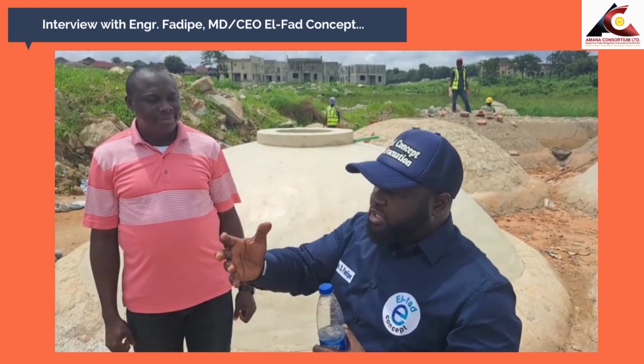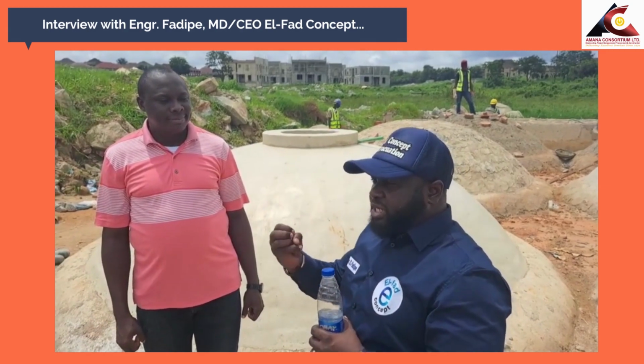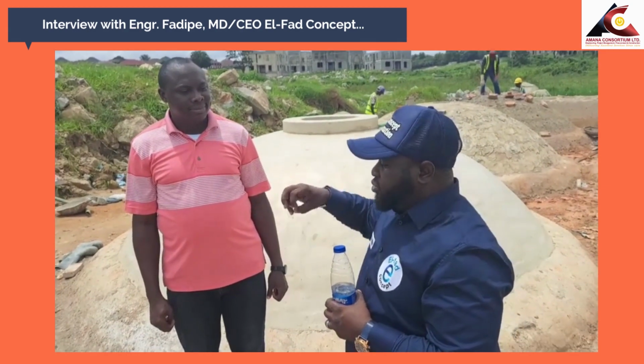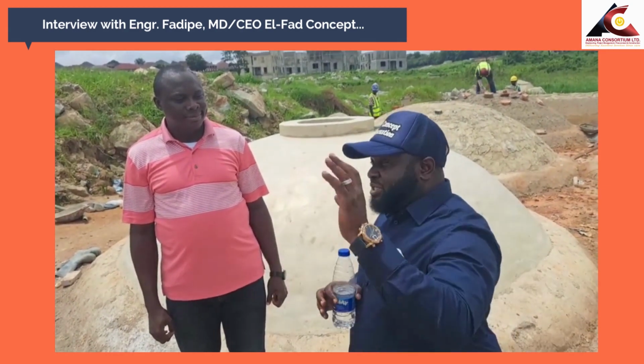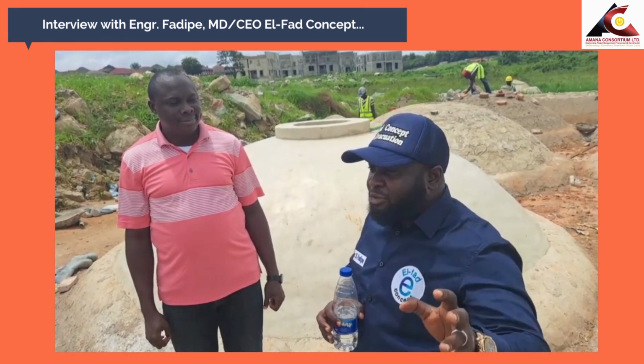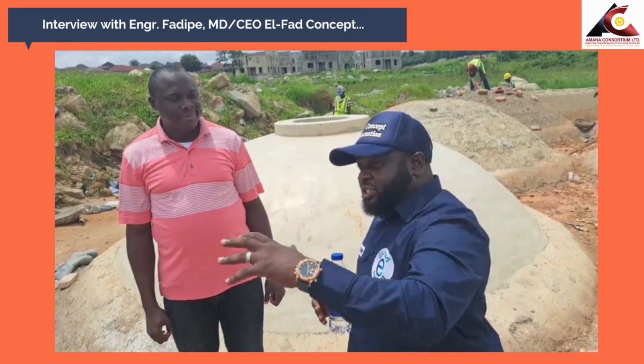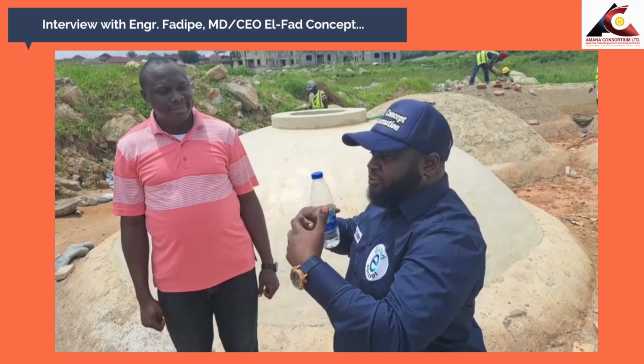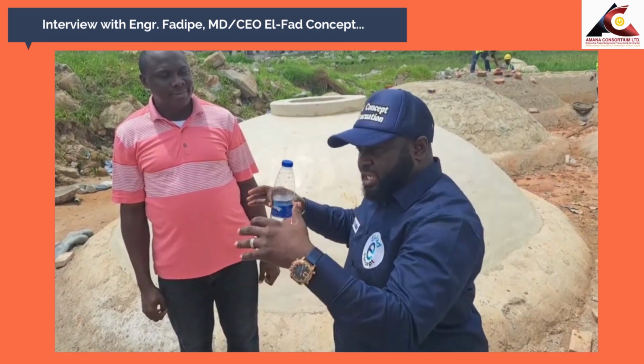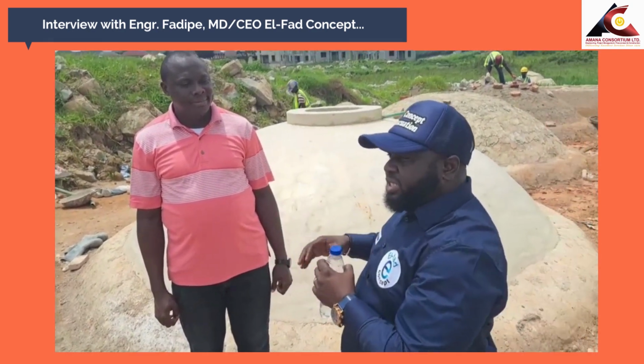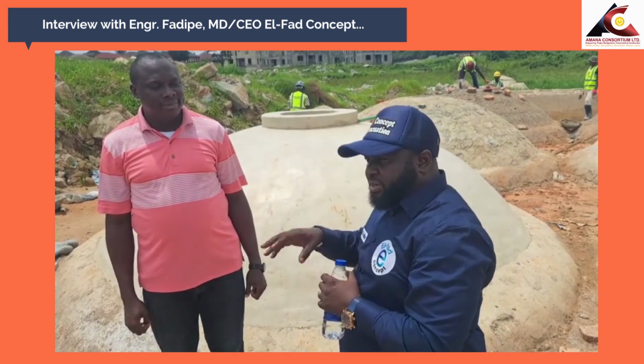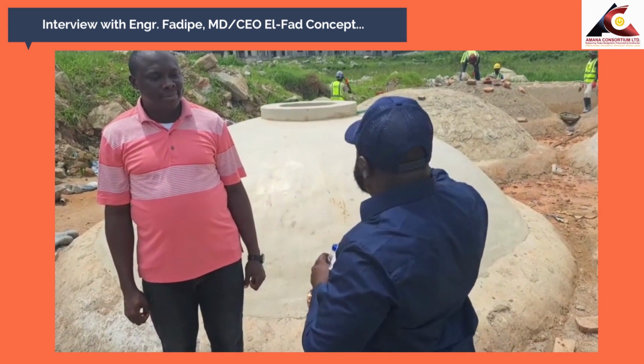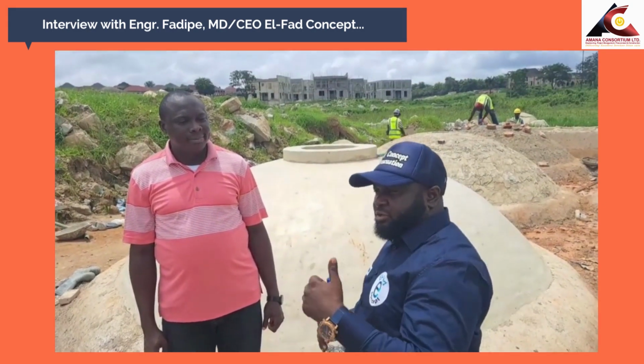So your solid, in the absence of oxygen, with the aid of bacteria, breaks down the sludge into water and gas. Remember that the aerobic system also has bacteria that break it down, but you blow in oxygen, which generates the bacteria or the flux, which will break down the sludge and treat the wastewater. But in the anaerobic system, you have anaerobic bacteria that break it down, and at the end of the day, you get biogas, which is one of the byproducts.